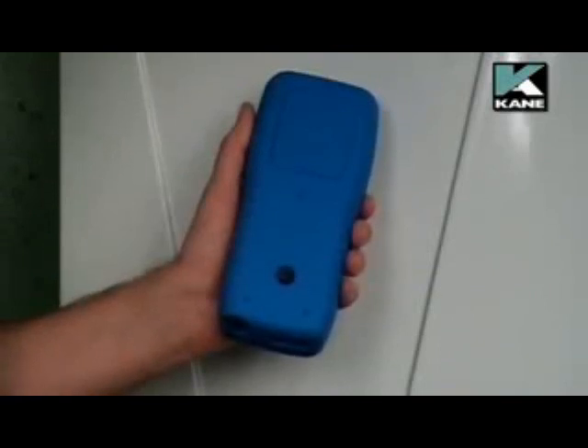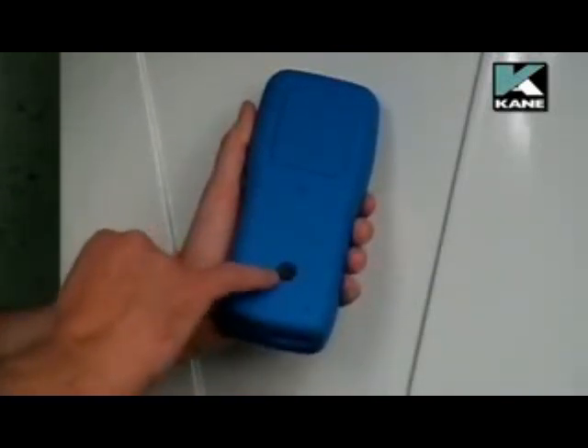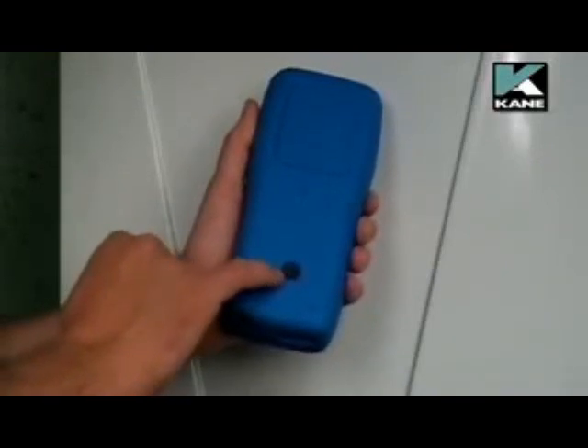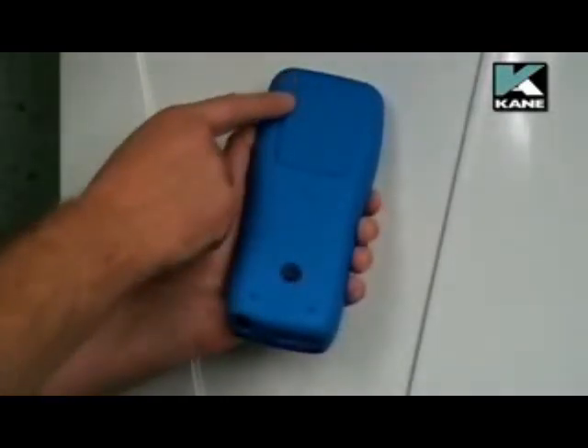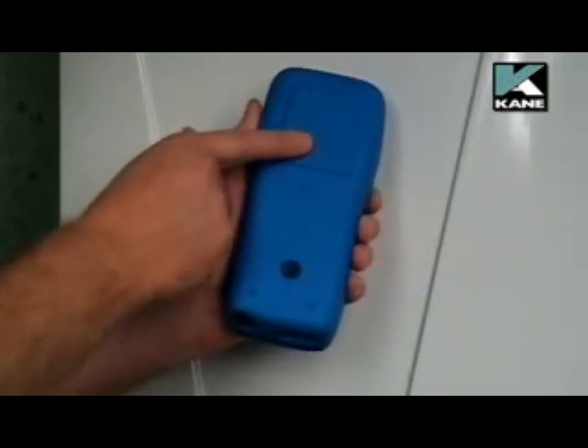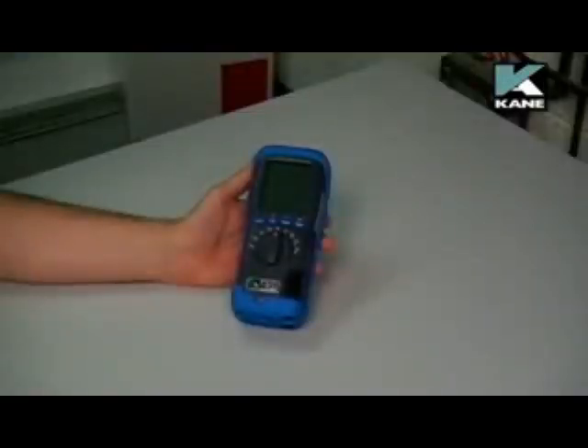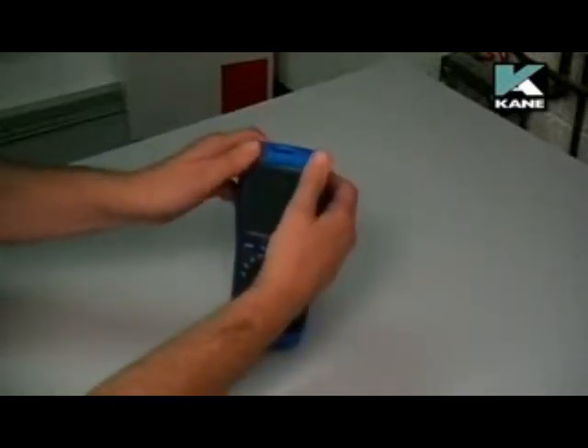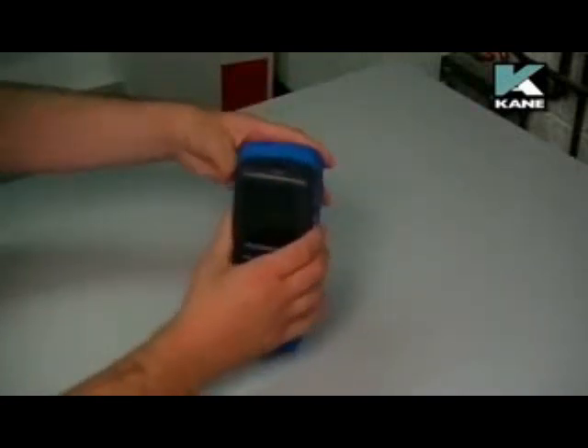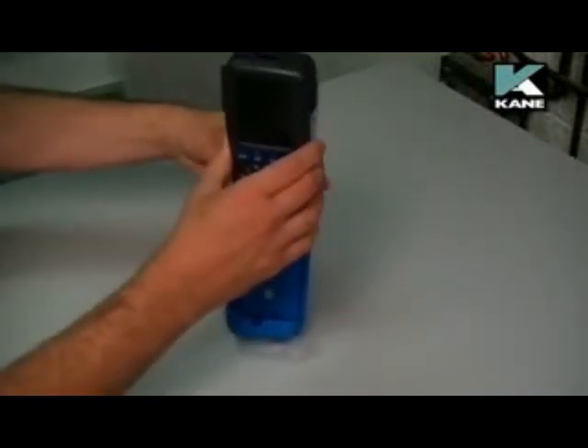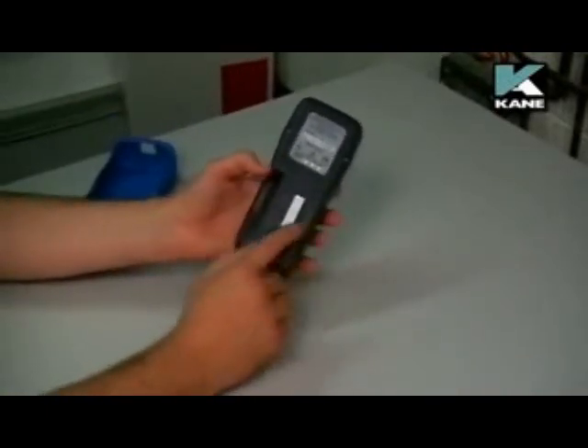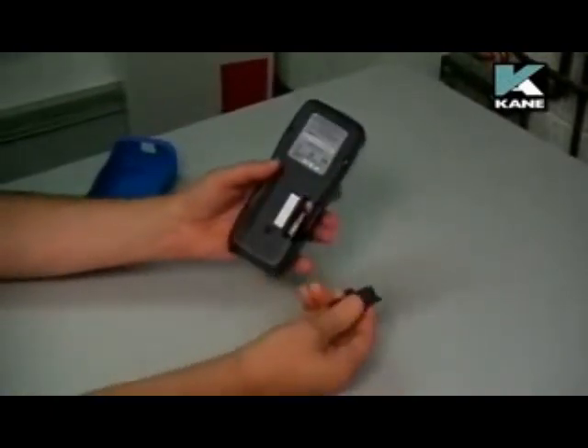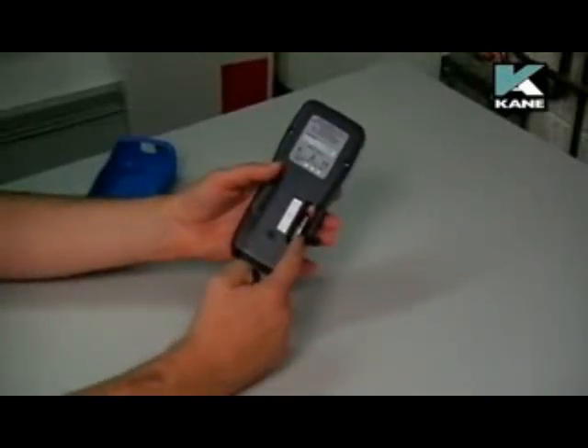On the back of the analyzer, this is the exhaust port for the flue gases. Here you have 2 magnets to actually attach the analyzer to a metal surface. To change the batteries or to change the particle filter, you must first remove the rubber boot. The easiest way to do this is to remove it at the top and then pull the analyzer up away from the boot. On the back of the analyzer, this is the battery compartment. Just undo the cover and you can get to the AA batteries.